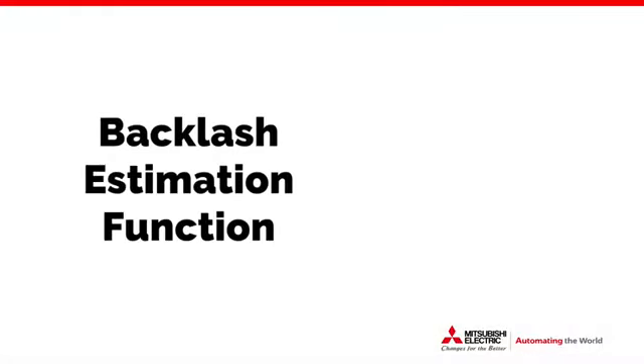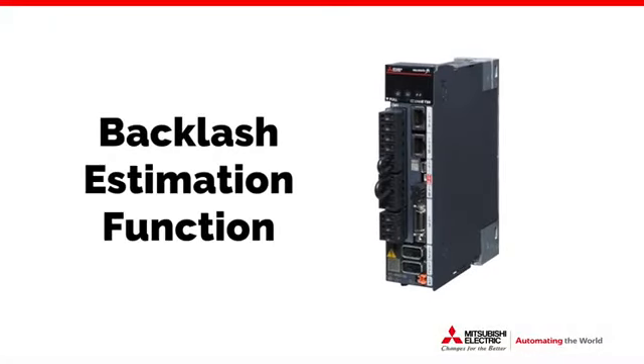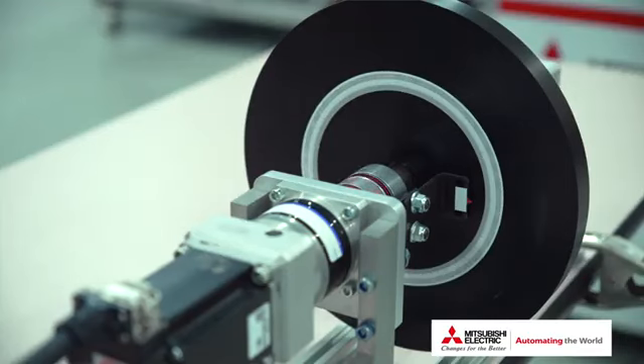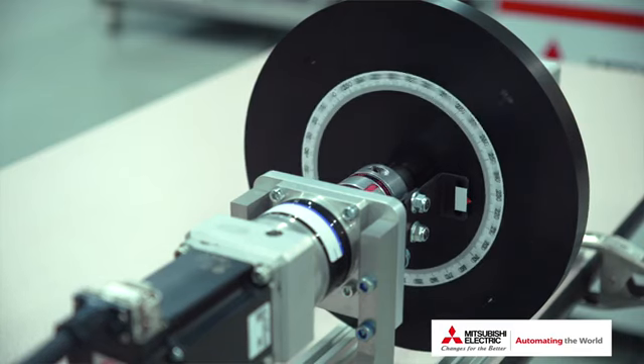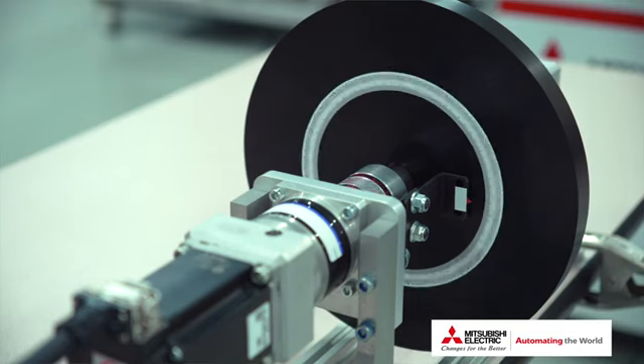Mitsubishi Electric's solution to this problem is our backlash estimation function, a standard feature on our MR-J5 servo amplifiers. The backlash estimation function rotates the servo motor back and forth at four points along the available travel of the machine. By measuring the motor feedback, the servo amplifier is able to approximate what the backlash of the machine is. This whole process can be done in just about two minutes and just a few clicks. Let's take a look at what that process looks like.